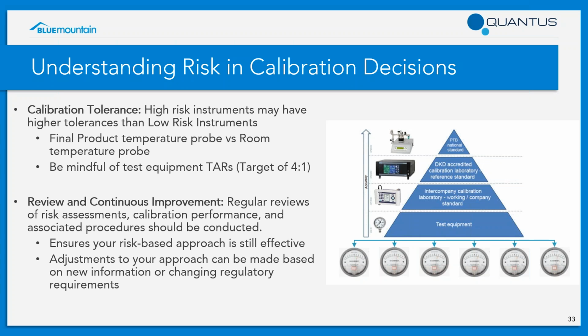Whenever you're assigning those tolerances, you're going to make sure you consider that the calibration instrumentation can keep what we typically like to see, what we call a 4-to-1 accuracy ratio, where the equipment you're calibrating with is 4 times more accurate than the device you're calibrating. That way, if your standard were to be out of tolerance during calibration, there's not a direct immediate impact on all the other devices that standard calibrated throughout its life cycle.